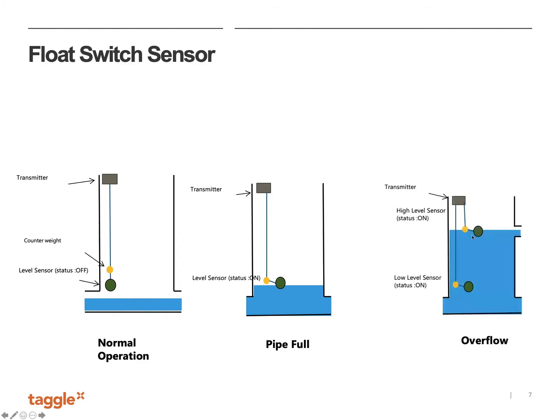By installing a second float switch and setting its threshold level at the overflow, this second float will tell us that there is an alarm state. We're now discharging sewage into the public, into the environment, potentially impacting the public, which is ideally something we really want to prevent. The first switch gives us some pre-warning that the second event may be occurring. Now, it doesn't have the resolution of other sorts of level sensing, which I'll show you a little bit later, but it does have that advantage of simplicity.